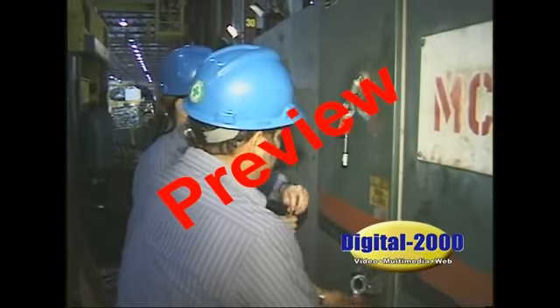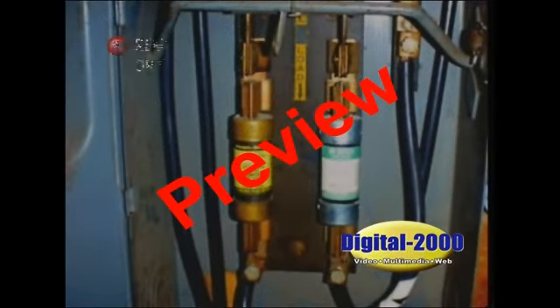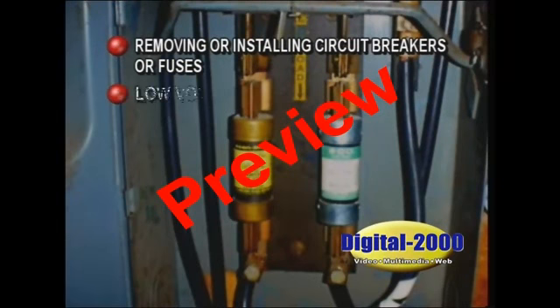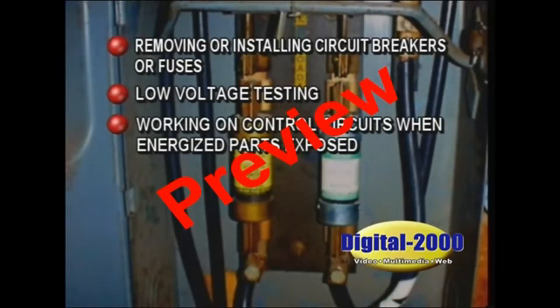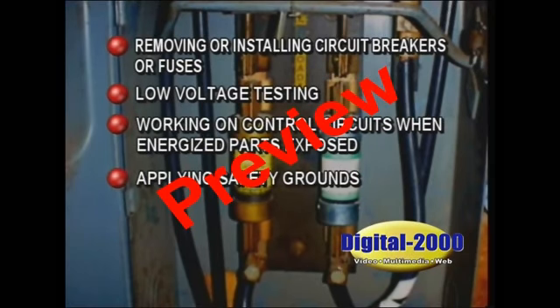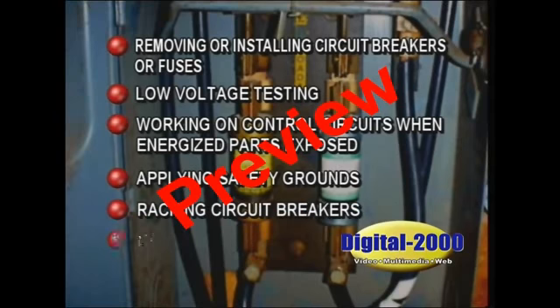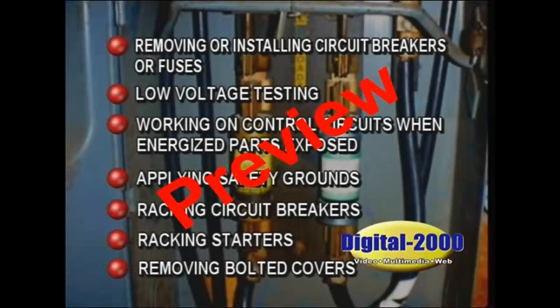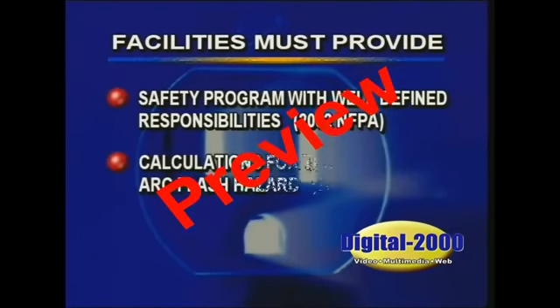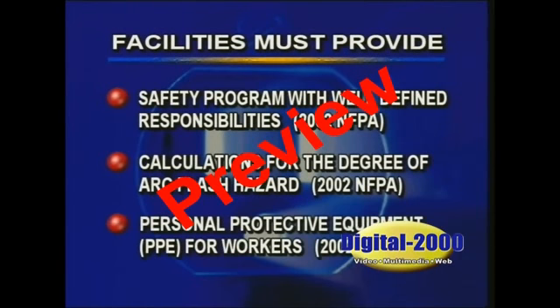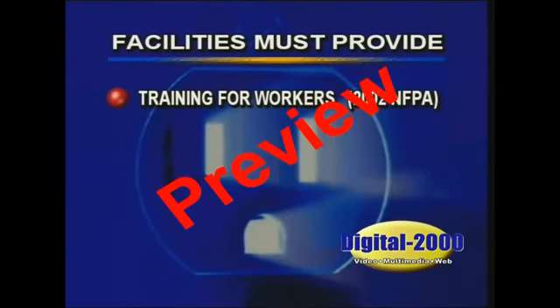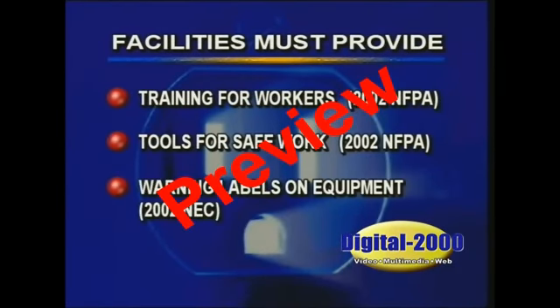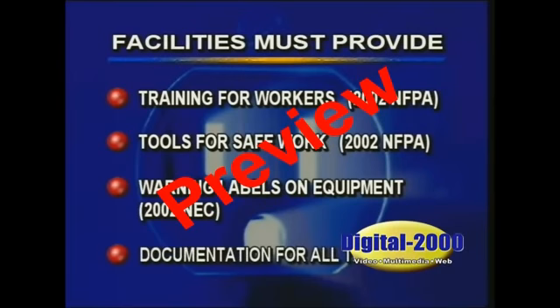Examples of tasks that require flame-rated clothing under NFPA 70E are removing or installing circuit breakers or fuses, low voltage testing, working on control circuits when energized parts are exposed, applying safety grounds, racking circuit breakers, racking starters, and removing bolted covers. The 2002 NFPA 70E and the 2002 NEC state that facilities must provide a safety program with well-defined responsibilities, calculations for the degree of arc flash hazard, personal protective equipment for workers, training for workers, tools for safe work, warning labels on equipment, and of course, documentation for all of these items.